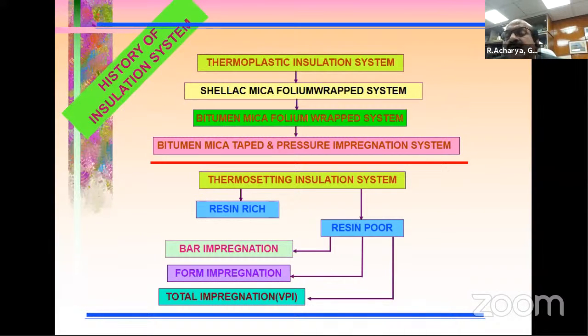If you see the history of insulation materials used in generators, I have given some examples of 30 megawatt generators way back in 1947, or a 60 megawatt generator - those days it was very large. But if you see the 100 years of the insulation system, broadly there is a red line I have written. Prior to the 1950s, or at the most 1960, the insulation system used in the turbo generator stator winding was basically a thermoplastic insulation system. The one practiced from the 1960s onwards is a thermosetting insulation system. Broadly, there are two different eras.